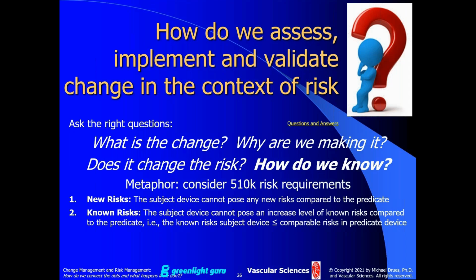Simply apply the two 510K risk requirements. Does the change create new risks in your device compared to the previous version of your device? That's requirement number one. And requirement number two, does the change increase the level of any of the risks in your new version of the device compared to the previous version of the device?